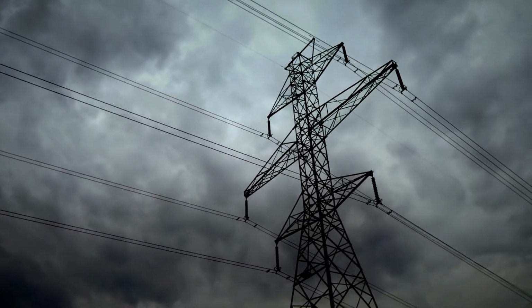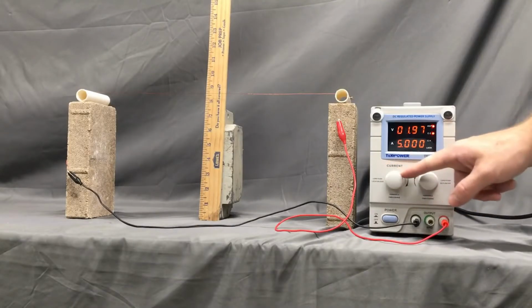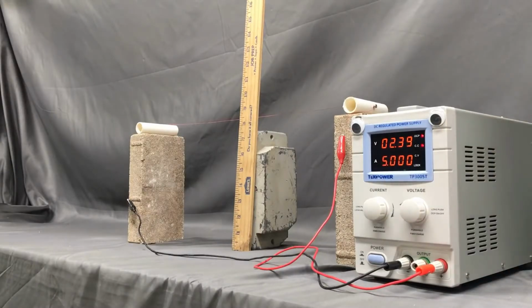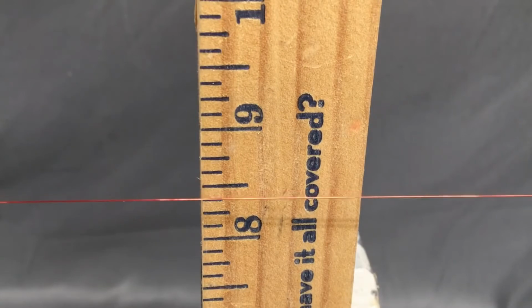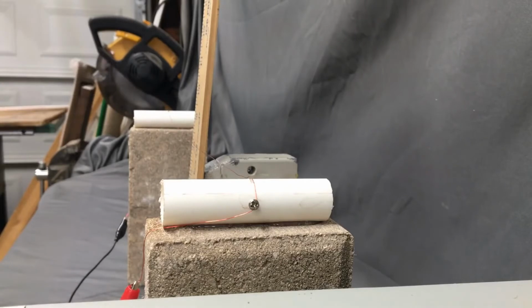One common type of fault on transmission lines comes from sagging. During peak demands, these lines move tremendous amounts of electricity as electrical current. Well, no wire is a perfect conductor. They all have some resistance. So the more current you try to pass through a wire, the less efficiently it works. That energy that doesn't make it to the end of the line is instead lost as heat. And what does heat do to metal? It causes it to expand. So the lines get longer, which means they sag lower, and occasionally that brings them into contact with tree limbs, creating a path to ground and shorting out the line.